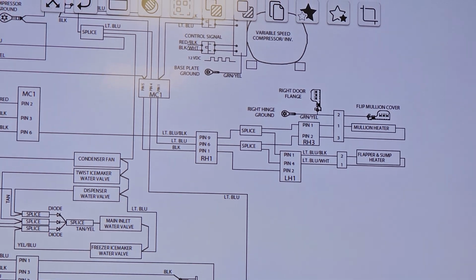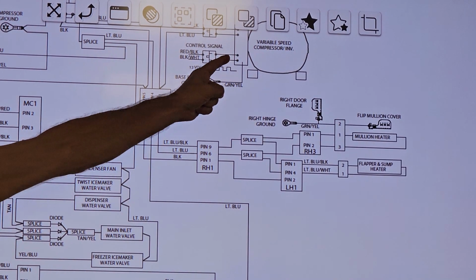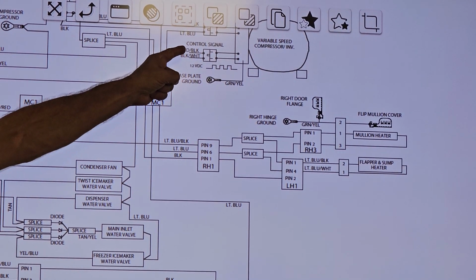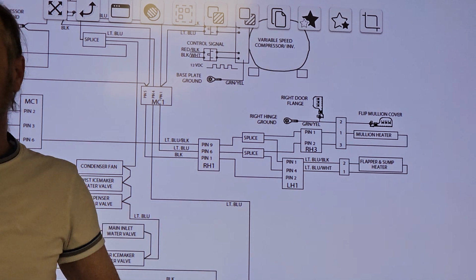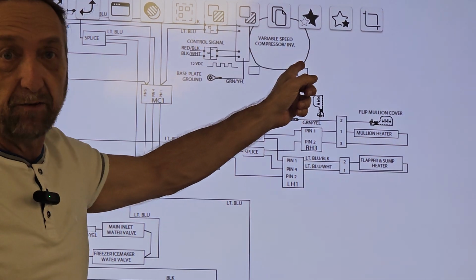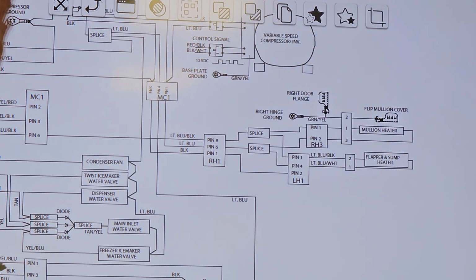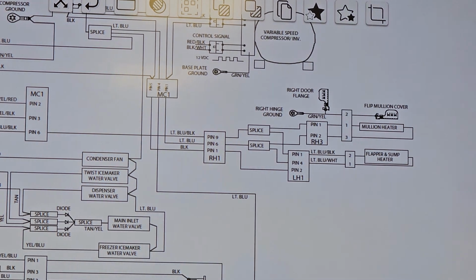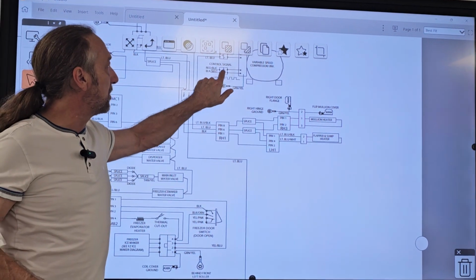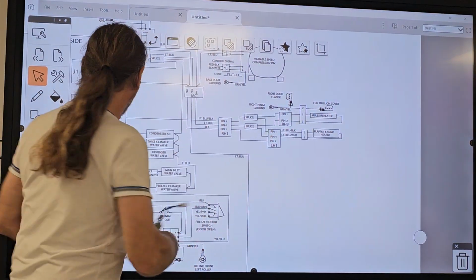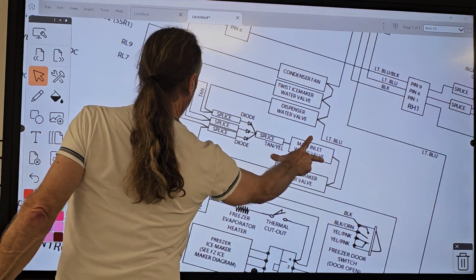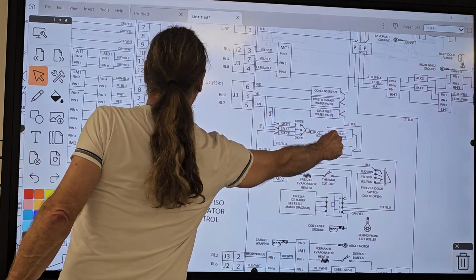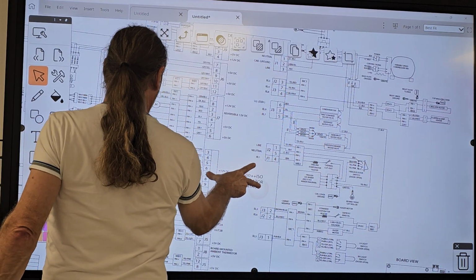But that 1 and 2 is that plug right there. Those two wires right there. Notice that the two wires aren't connected to anything. Why did they draw it like that? Because the compressor has 120, but remember the board, the low voltage side of the board's over here. So how much voltage should I have there? Well... I know this board update really screwed up my thing.